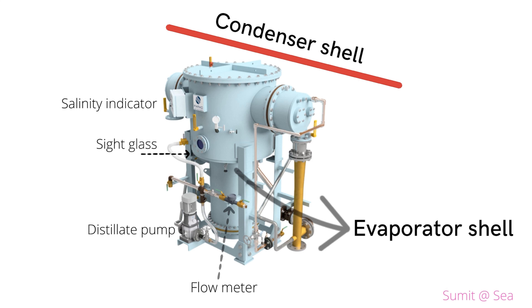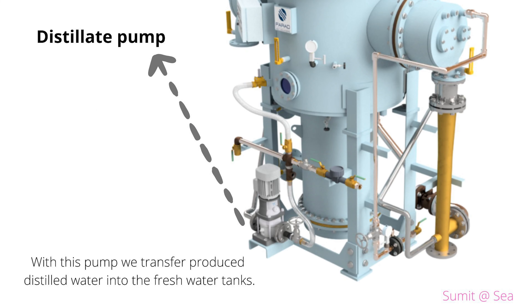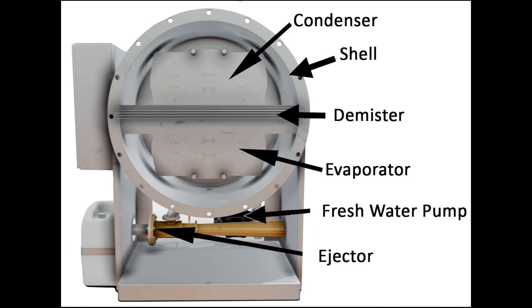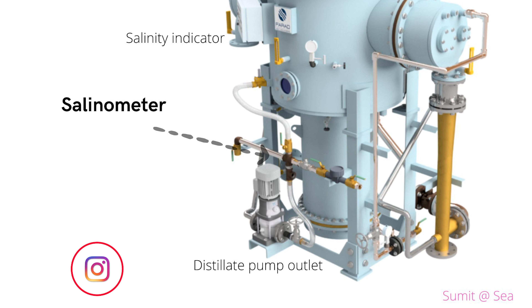Number three is the distillate pump, which transfers the produced fresh water to the fresh water tanks. Number four is the ejector pump — the ejector, driven by the ejector pump, creates vacuum inside the shell. Number five is the demister — a thickened layer of mesh structure fitted between the condenser and the evaporator element, used to separate seawater droplets from the steam vapors.